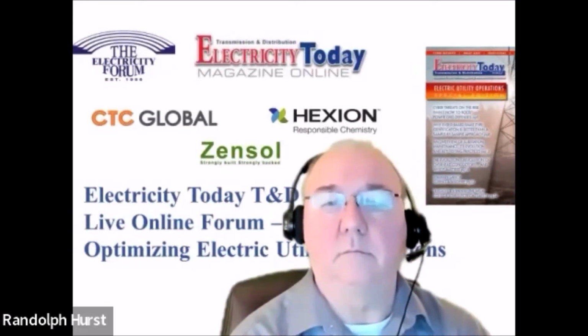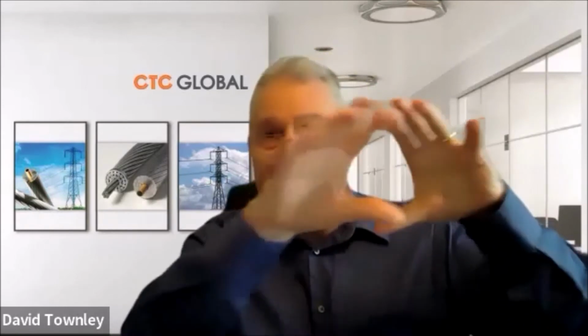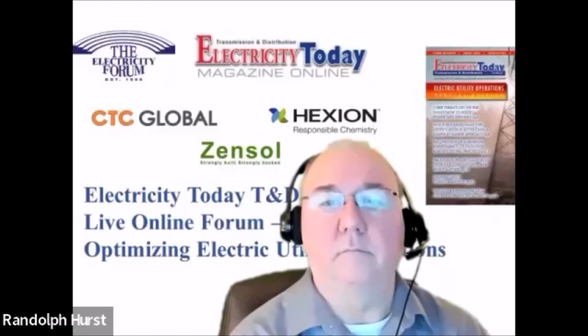Mm-hmm. And your towers, of course, the size of your towers was, I'm going to run it at an emergency rating. It's going to sag this much with that current. I need a safety of this much. Mm-hmm. Voila, that's my tower. So when you start overloading, you're running the risk of actually safety violations and ground clearance violations.